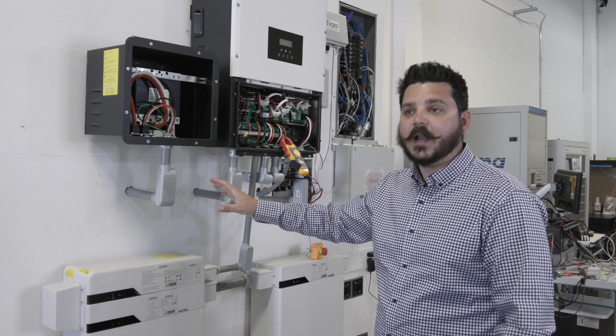So the first device you see right here is called a transformer, and what this does is allow the system to create a neutral-forming grid. That's really crucial for backup situations. You cannot have a backup battery system without a transformer because you need that neutral to be formed for a grid. If there's no grid, you have no neutral, no backup. So this is really important.